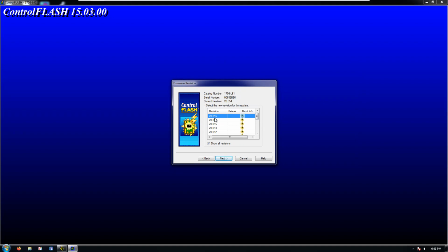And if you had quoted your customer, yeah, I can come in and flash the firmware of that controller, no problem. It'll be a day's labor to come out and flash it. Well, then you show up and you find out, oh, well, yeah, you can't flash it because it's an old controller. It can't take the new one. Sorry, your $700 for a day's work is actually going to be $15,000 for a new controller. You really got to pay attention to that.